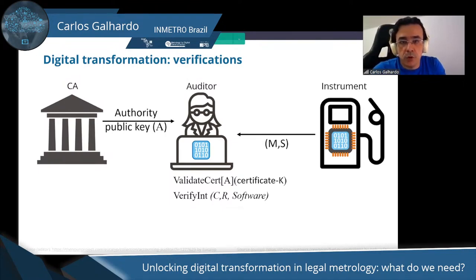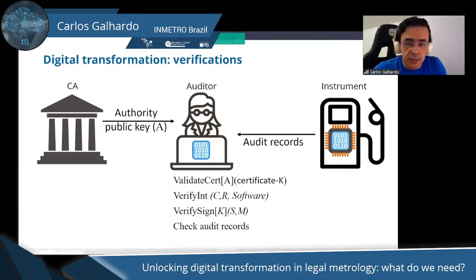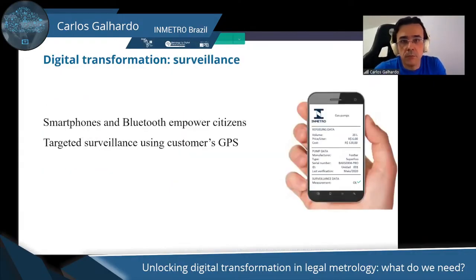Next, the auditor performs a measurement and collects a digitally signed measurement result. They verify the digital signature. And the auditor collects the audit logs and checks for any suspicious activity, for example, too many changes in calibration parameters. With Bluetooth technology, any customer with a smartphone could connect to the instrument, request measurement result data and verify the digital signature. The smartphone could transmit the requested data and GPS location to Inmetro, creating a database for further surveillance operations.